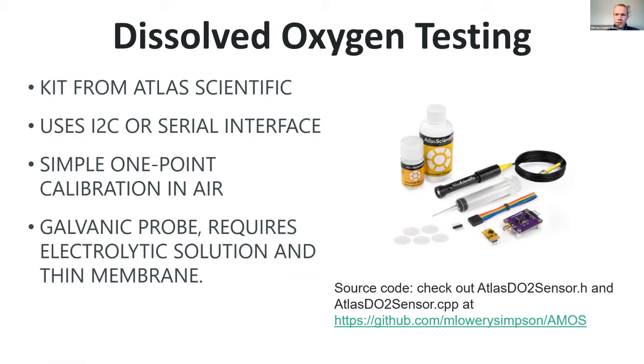So that was easy too. You can also do a 2-point calibration, but so far I haven't tried that one yet. And this is a galvanic probe, so it uses an electrolyte solution within the probe and basically a very thin membrane on the end of the probe. And so by measuring when oxygen molecules in the water basically get transmitted through the thin membrane and produce a current and a voltage within the probe, the voltage is measured and you get your dissolved oxygen reading that way.